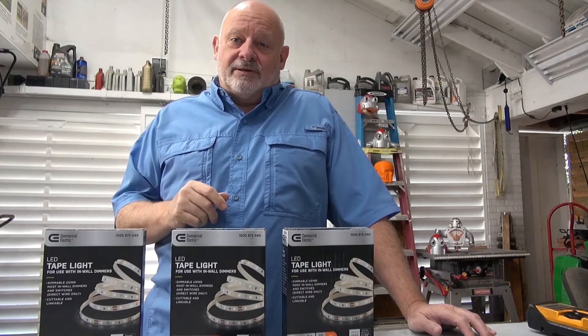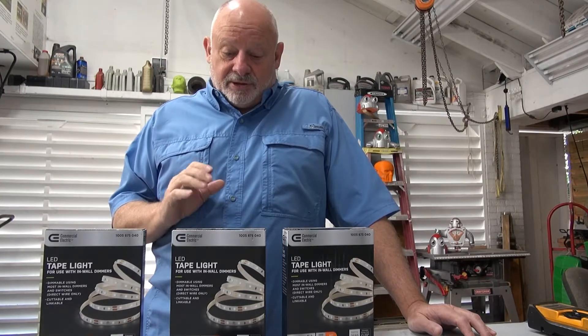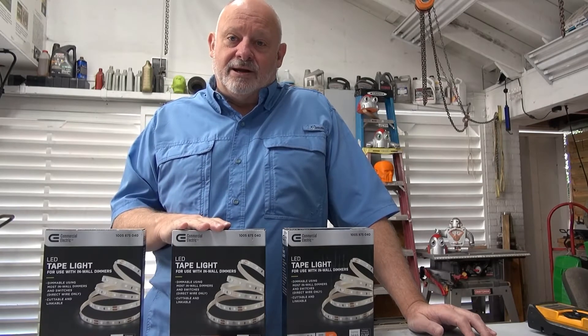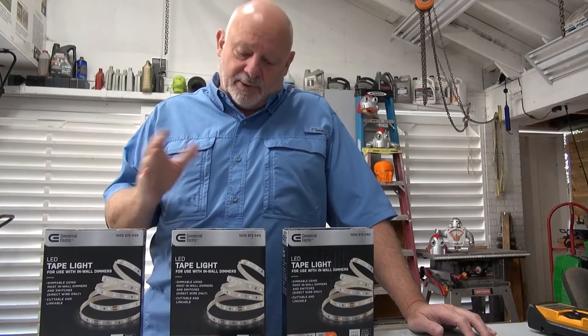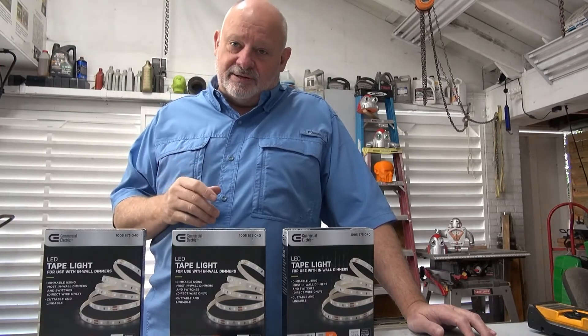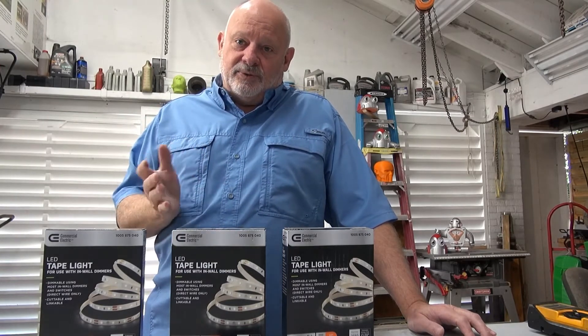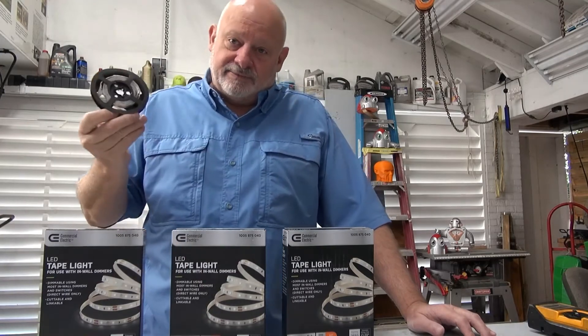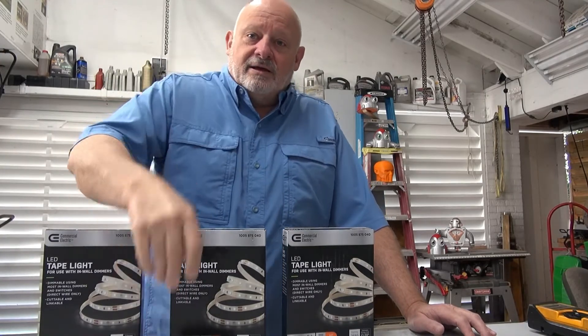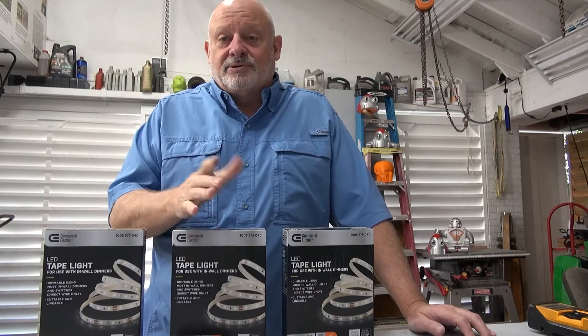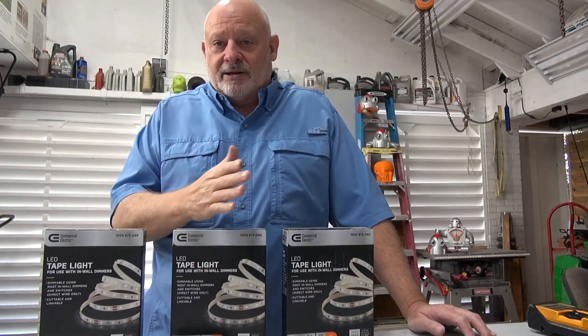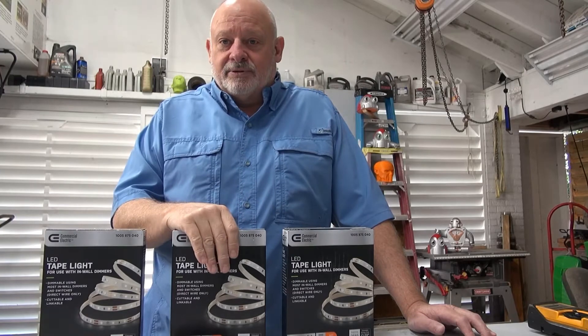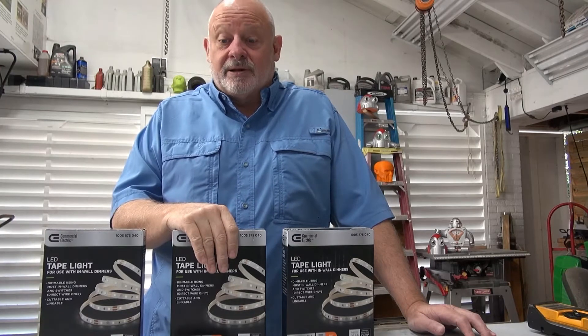I want to check and make sure that I won't be exceeding the rated output of the power supply. So I'm going to hook one of these up and measure the current required under full load, then add an extra couple feet of load and measure the current to make sure I'm not approaching the rated output.